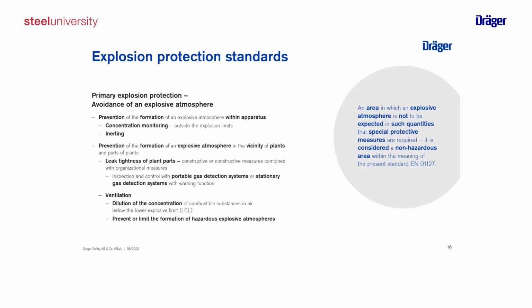On the one side, we have to look at the formation inside a machine or apparatus, where we have an enclosed environment, and there we can easily measure the concentration and keep it below the explosion limits. In cases where we have high concentration, we can use inert gases, so we reduce the oxygen level inside so that the third element needed for an explosion is not present. But if you go this way, you need sensors to control the oxygen level inside your process.